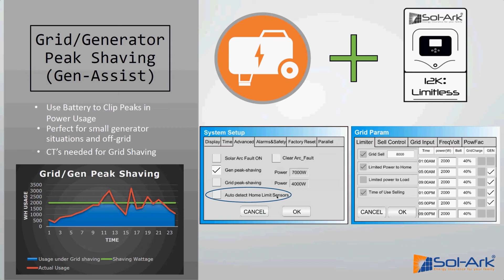Okay, so as for generator, Gen Assist, it's the same thing as grid shaving, but it's really useful for smaller generators. So you can set your threshold value to protect the generator. If you're charging off the generator and maybe it's an 8,000 or 9,000 watt generator, you'll want to set the threshold value 1,000 or 2,000 watts below whatever the generator's maximum output is rated for. And then the batteries will start discharging instead of charging if the generator hits that value. And that's a good way to pass the AC power through the system to your loads and charge without overloading an undersized generator connected to the solar.